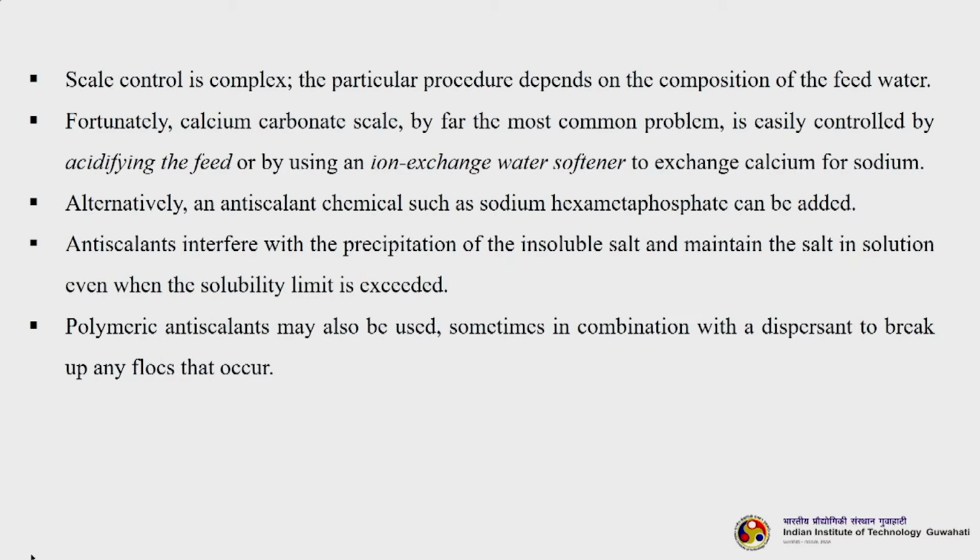Scale control is complex. The particular procedure depends on the composition of the feed water. Since the feed water composition varies, scale control is a complex phenomenon. Fortunately, calcium carbonate scale, by far the most common problem, is easily controlled by acidifying the feed or by using an ion exchange water softener to exchange calcium for sodium.